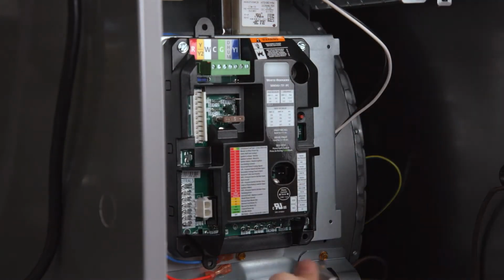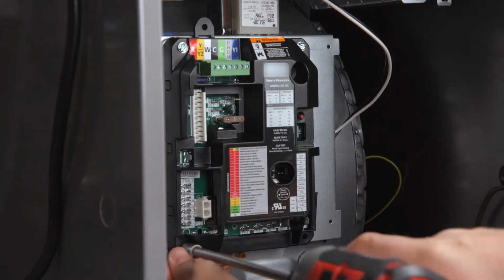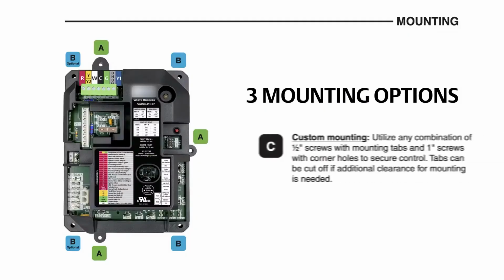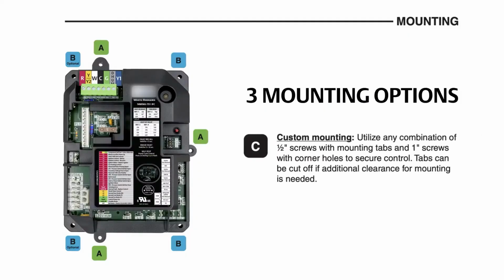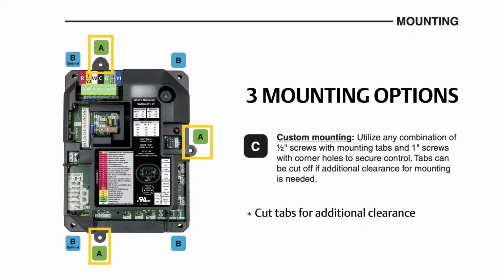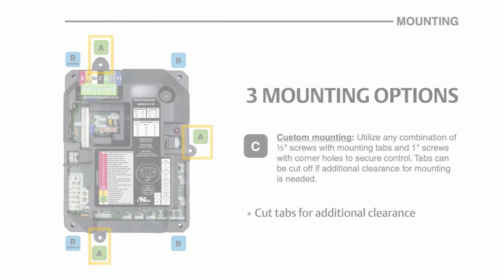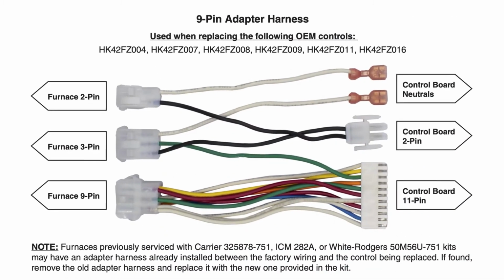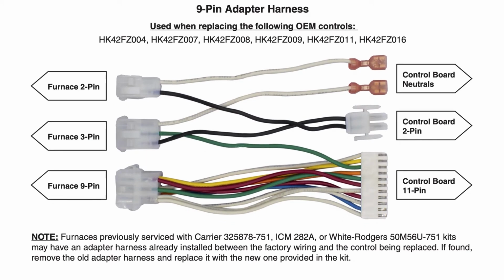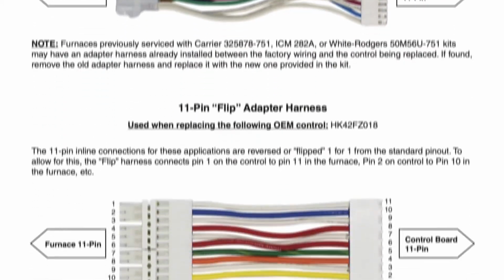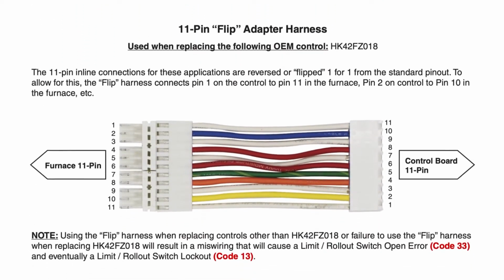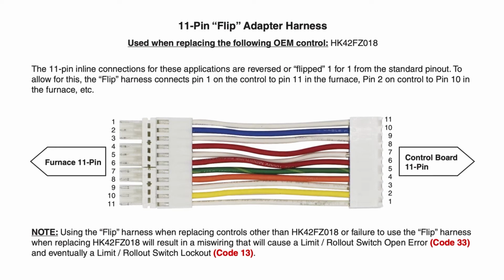Be careful when drilling to ensure nothing gets damaged behind the sheet metal. You may also utilize any combination of 1/2-inch screws with mounting tabs and 1-inch screws with corner holes to secure the control. Tabs can be cut off if additional clearance is needed for mounting. Most furnaces are serviced by simply connecting the OEM wire directly to the new control board. The installation instructions show which, if any, adapter harnesses are needed.